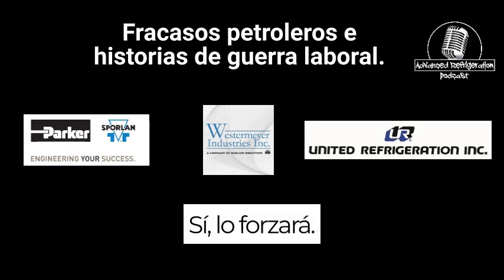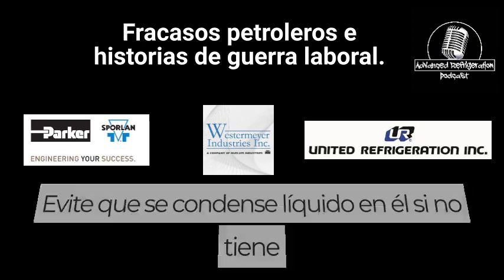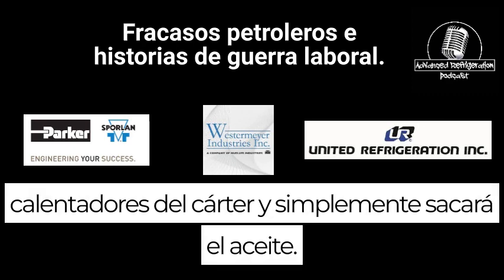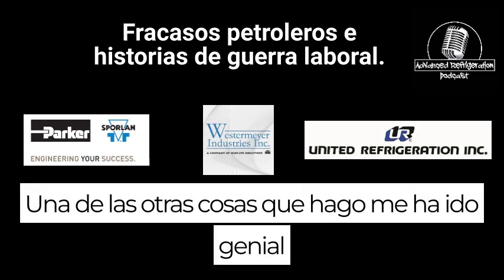Yep, it'll force it on, get some of that oil moving in there, get the compressor warmed up, keep liquid from condensing in it if you don't have crankcase heaters, and it'll just get the oil out of it. That way it's not filling up with oil. That's one of the other things I didn't cover, and I've had great success with that.